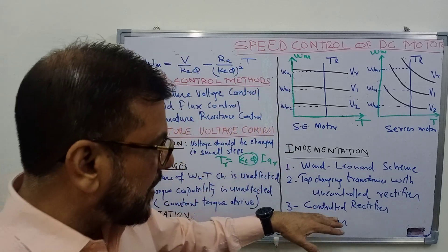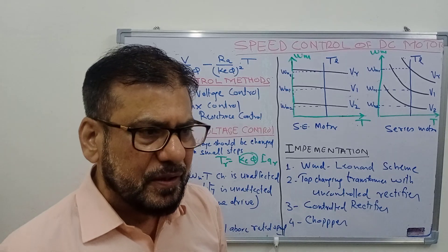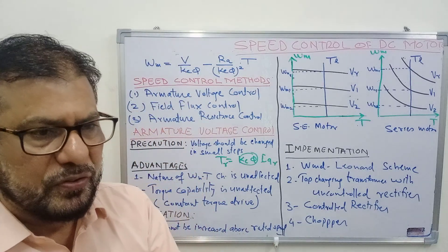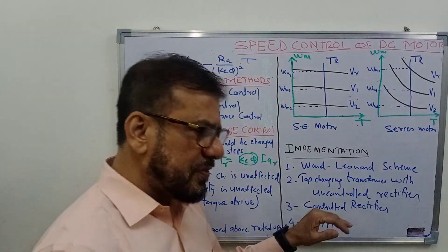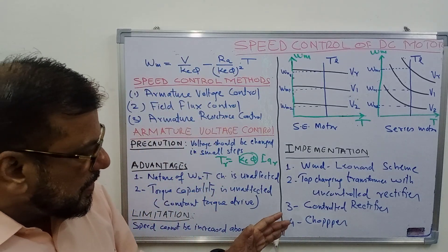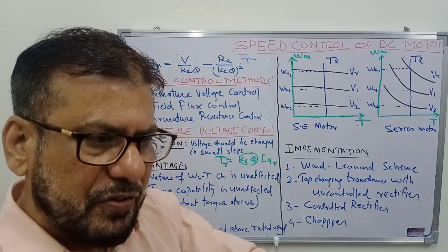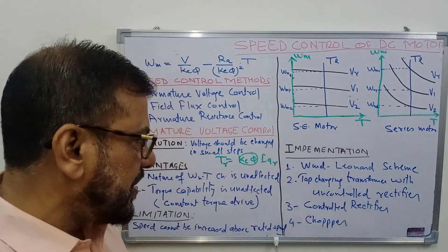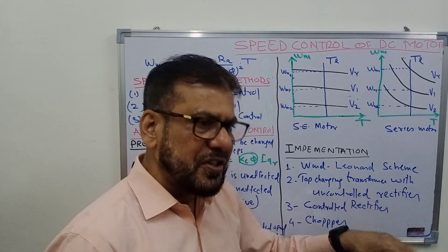A third implementation method uses a controlled rectifier with a thyristor bridge, where changing the firing angle of the thyristors changes the average output DC voltage supplied to the motor to control its speed. If the supply is DC, another option is a chopper (DC-DC converter), where changing the duty ratio changes the average output voltage and hence the motor speed. The controlled rectifier method and chopper control method will be discussed in detail in the coming lectures.